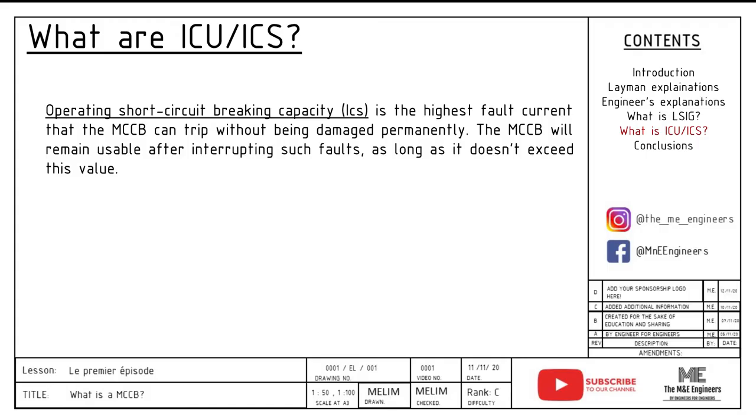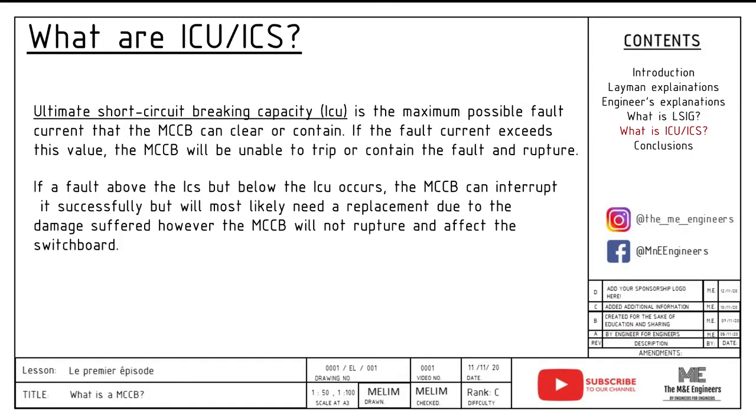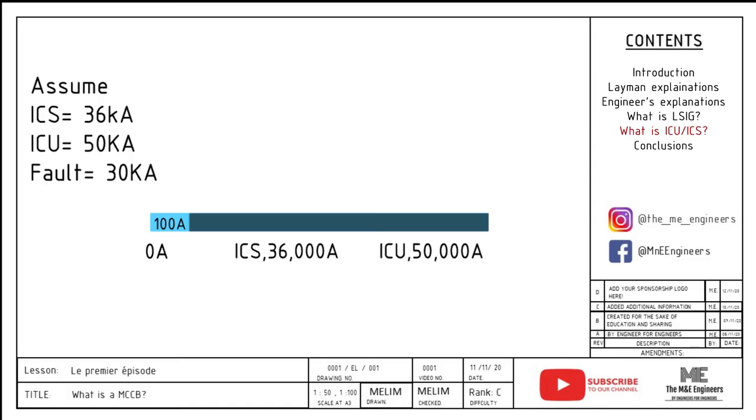Next, let me share a little about breaking capacity, ICU and ICS. First, we have ICS, the operating short circuit breaking capacity — this is the highest fault current that the MCCB can trip without being permanently damaged. The MCCB shall remain fully reusable after interrupting such faults as long as it doesn't exceed this value. Whereas ultimate short circuit breaking capacity, ICU, is the maximum possible fault current that the MCCB can clear or contain. If the fault current exceeds this value, the MCCB will be unable to trip or contain the fault, thus causing a rupture. If a fault is above ICS but below ICU, the MCCB can interrupt it successfully but most likely you will need a replacement due to damage suffered, though it will not rupture and affect the switchboard.